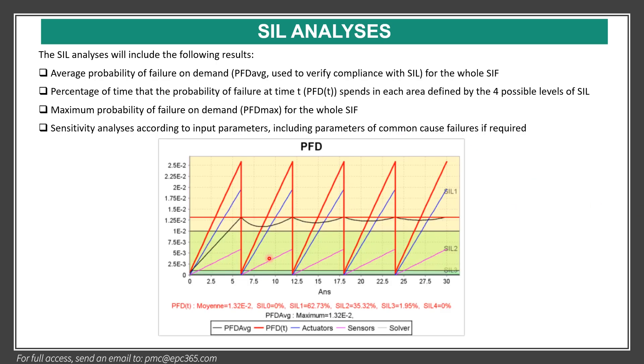This chart shows probability of failure on demand over the years, with actuator, sensor, and solver shown in different colors. By year, the PFD increases, and then after the test it decreases. The graph shows SIL 1 and SIL 2 boundaries, and the overall percentage of time in SIL 1, SIL 2, and SIL 3 zones. Certain software packages perform this analysis — Exida and GRIF, among others.